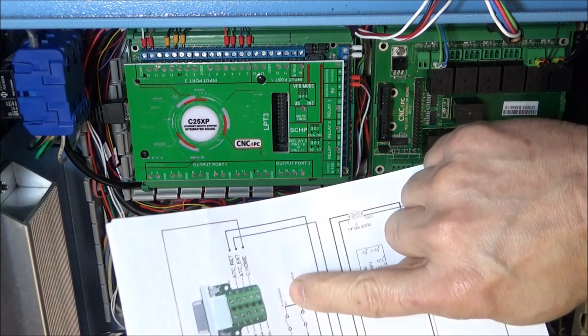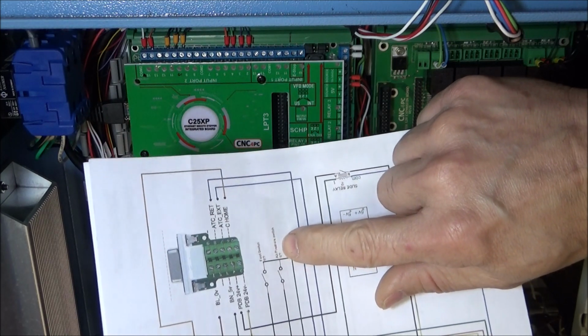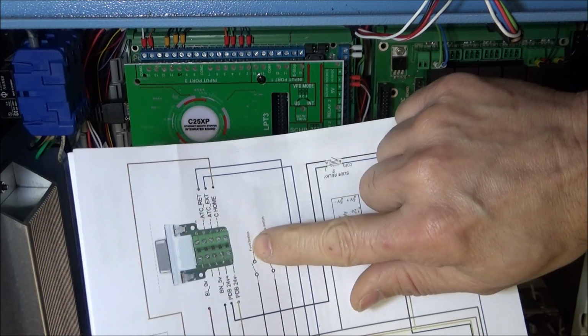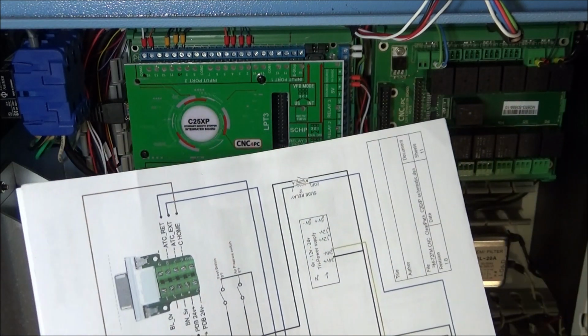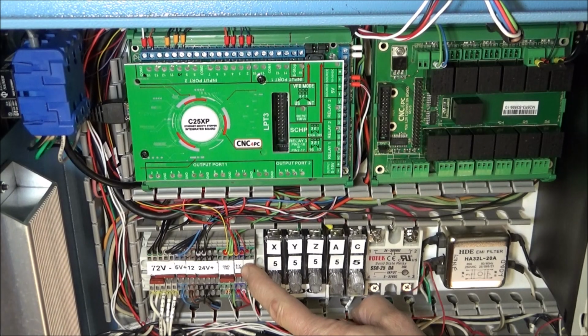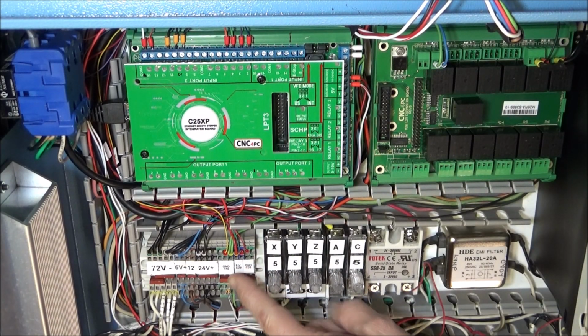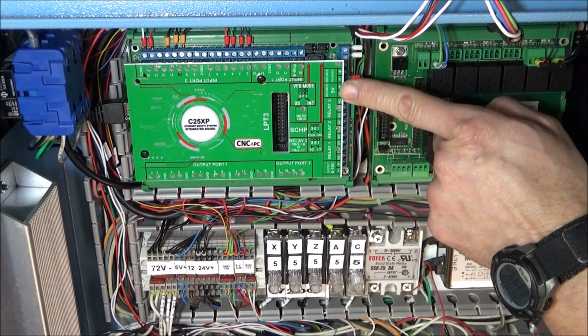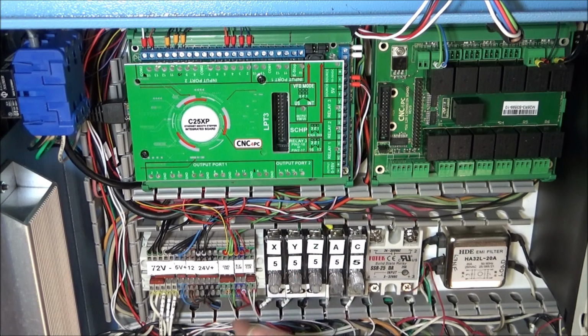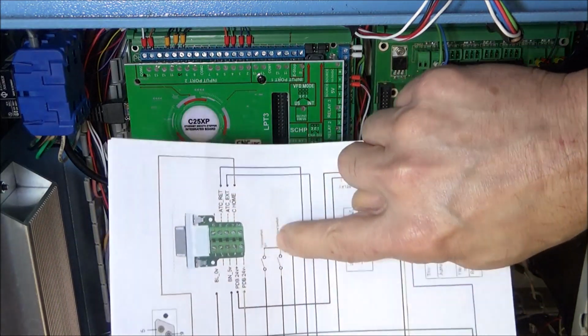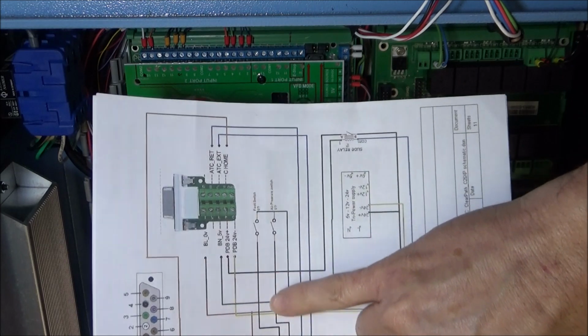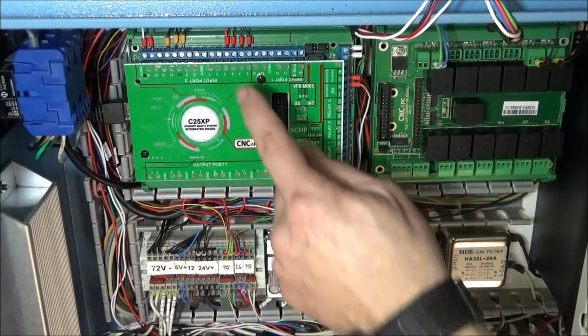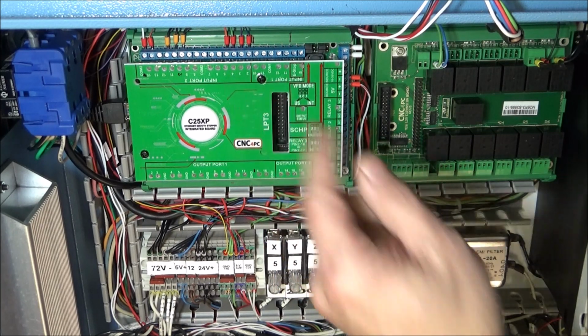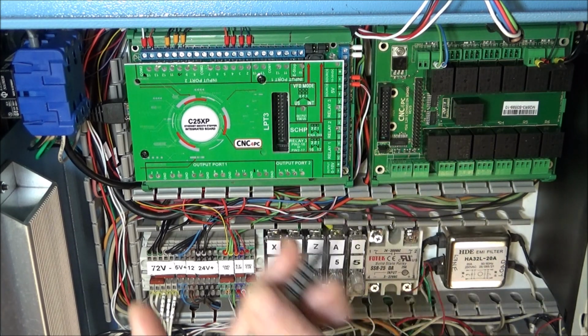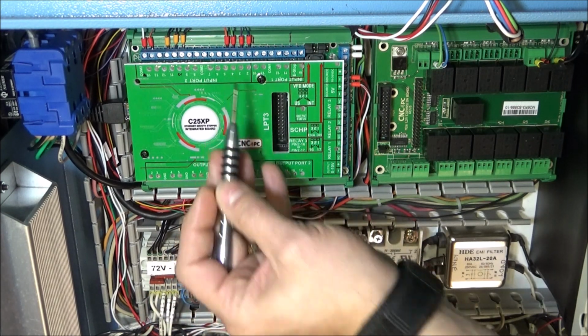So we installed our foot switch wiring and our air pressure switch wiring. The first thing we did was we brought 5 volts over to these switches from our C25 power source. Remember, this terminal block just connects straight to here on the C25. We brought power and landed it here so that we can bring it out to our devices. So we've brought our 5 volts out here to each one of these switches, and then our input 4 and 5 we've landed here and here. So we've got input 4 and then input 5.